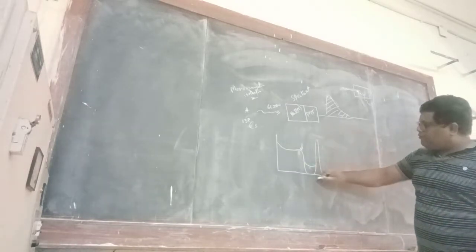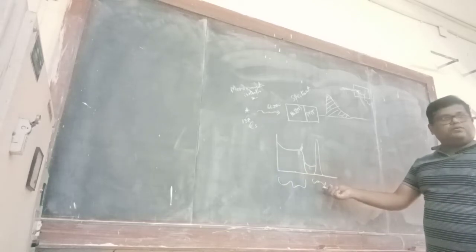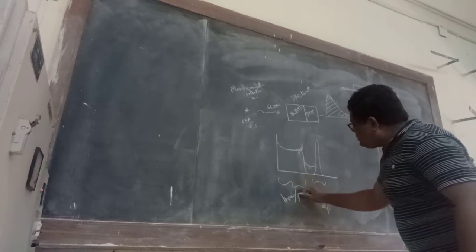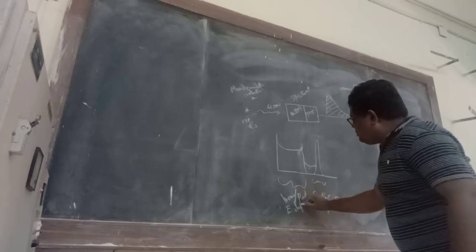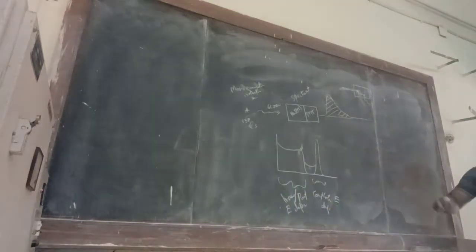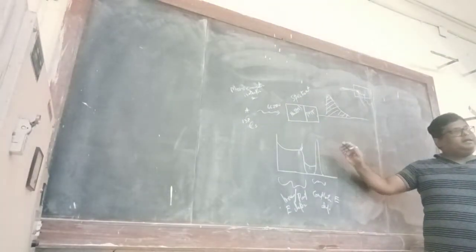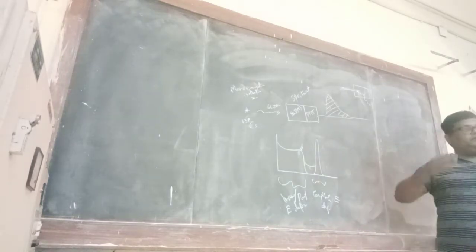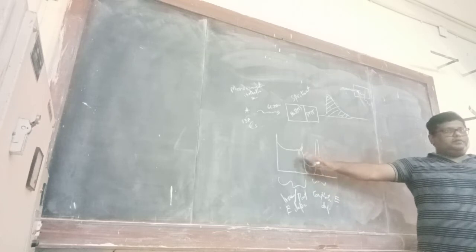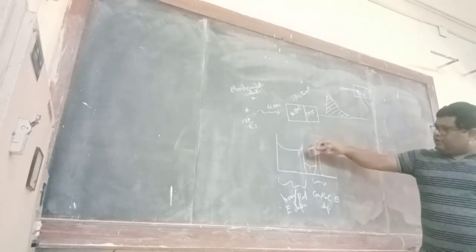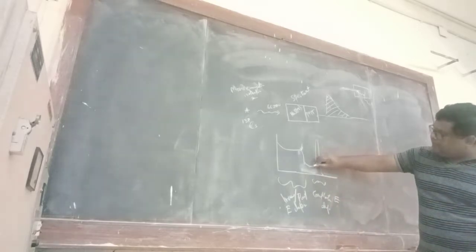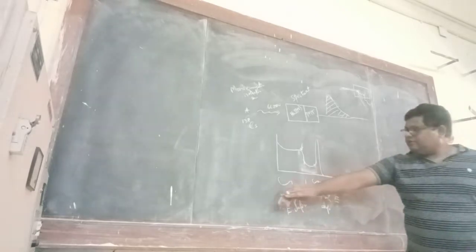So you see in this spectrum we have got two regions. One is the important one. This is the region of complete energy deposition, and this is incomplete or partial energy deposition. Okay sir? So we have got two regions. Now of course, which one do you want? We want this one. But it is not possible to get only this one. This will always be there. Of course there are other effects, and many techniques to reduce this part. Now, you will be amazed to know that in the experiment that we will be performing, we will get this spectrum. It's a very nice demonstration. Okay.